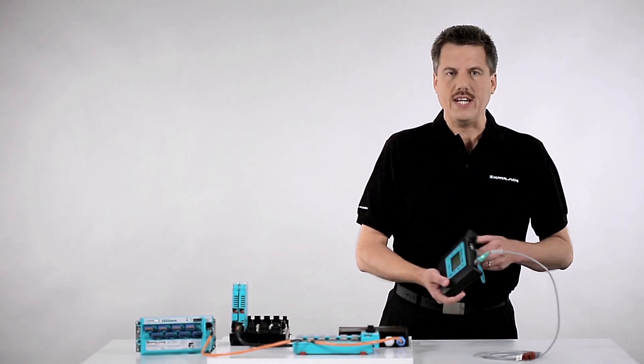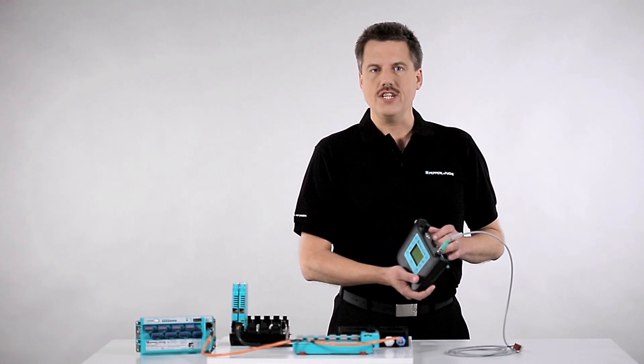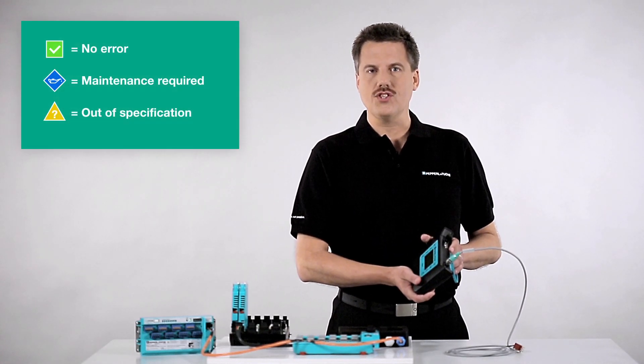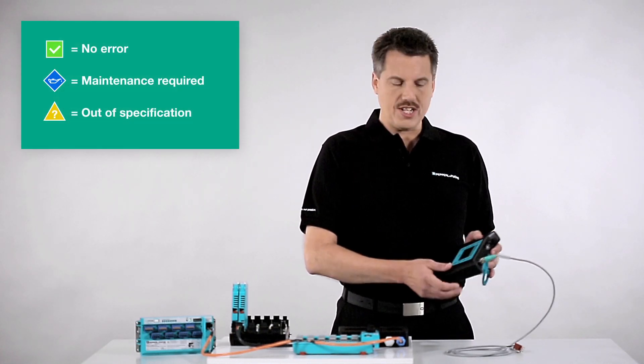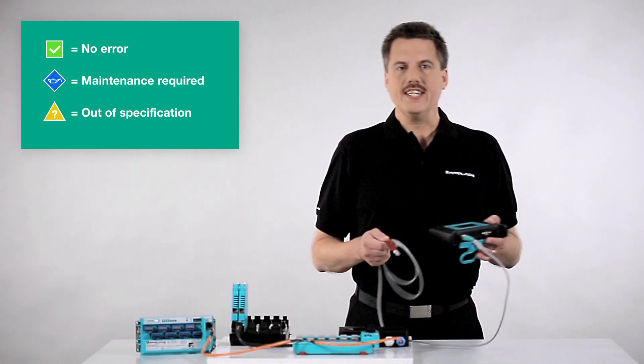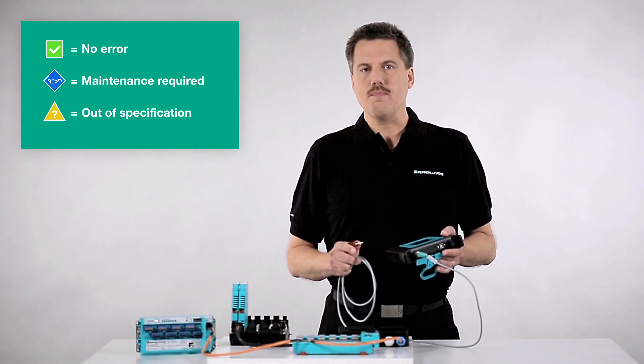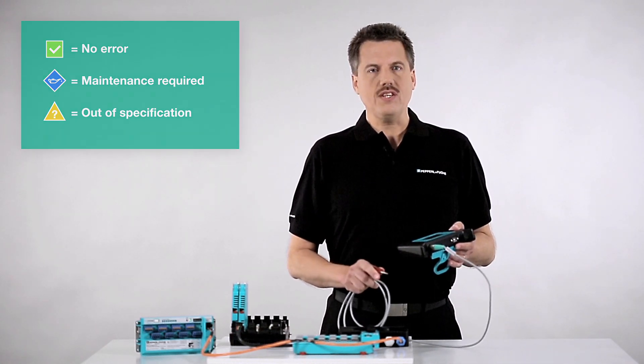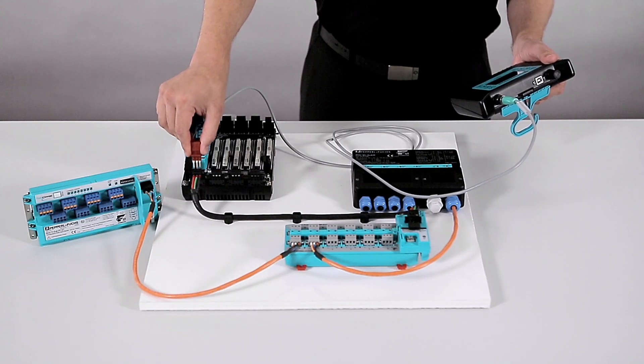The FDH1 rates the quality of our installation in accordance with NAMUR recommendation NE107. So let's check it out. We can connect the FDH1 at any point of the segment and the easiest way to do so is here at the power supply.